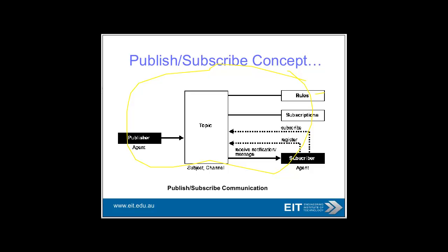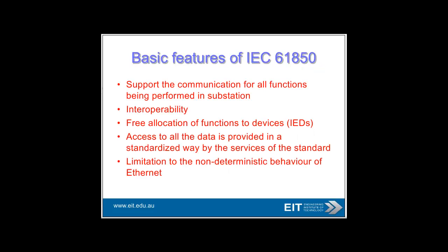With publisher-agent topics, you have rules, subscriptions, and subscribers who subscribe to the publisher's data — quite an important concept. The basic features of IEC 61850, which is the underpinning for substation automation, are obviously trying to support all functions in a substation, providing interoperability — meaning connectivity between different instruments and different devices — and obviously using things such as IEDs, which I'll talk about in a tick.